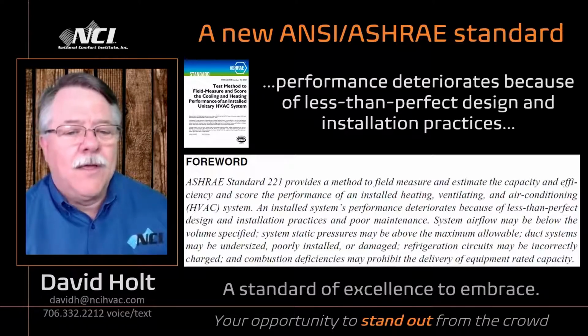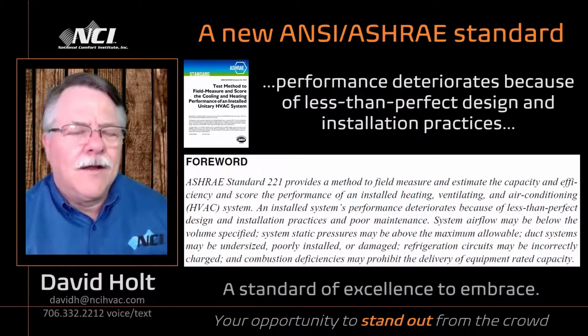All right, think about that one right there. So if I've got a 2.5 ton system, I'm supposed to be operating about 400 CFM per ton, depending on your market, of course. Let's just say 400 times 2.5, that's about 1,000 CFM that needs to be blown across the evaporator coil to make the air conditioner work, right? Well, what happens if you only have 570 CFM? Would that be adequate airflow to charge that system? Nope. Do you know how much air is blown across the evaporator coils for all those units you've put in?